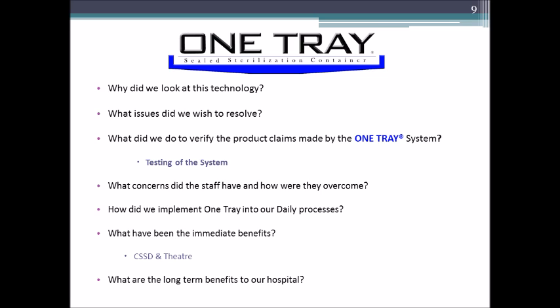Some of the times we would open up, you've got to understand, we were opening up these containers during our product testing immediately after they came out of the sterilizer. So we would look underneath that plate system, and sometimes there would be a couple of droplets of retained moisture.